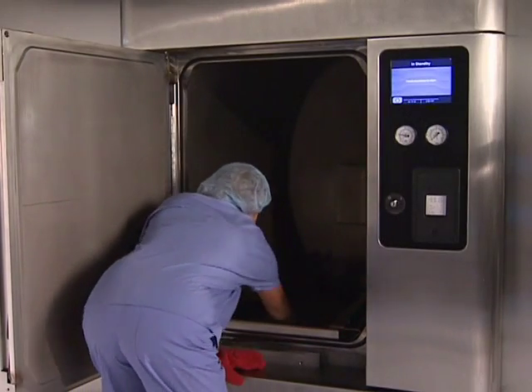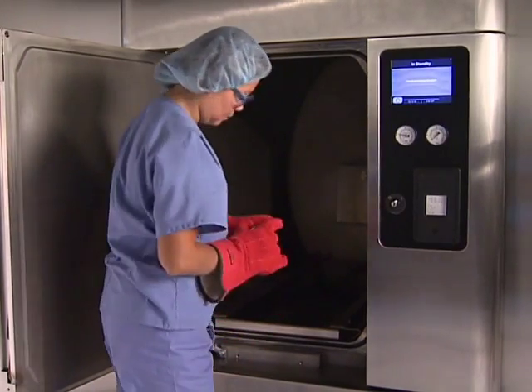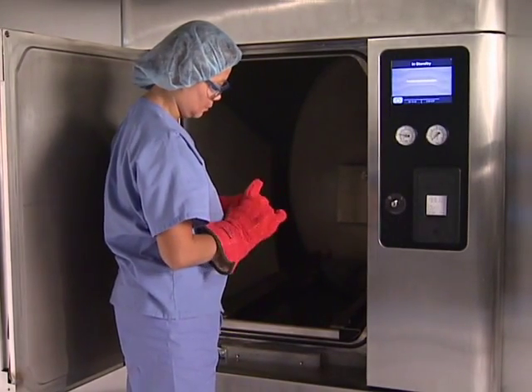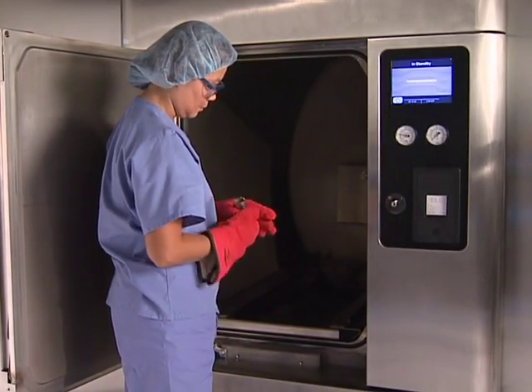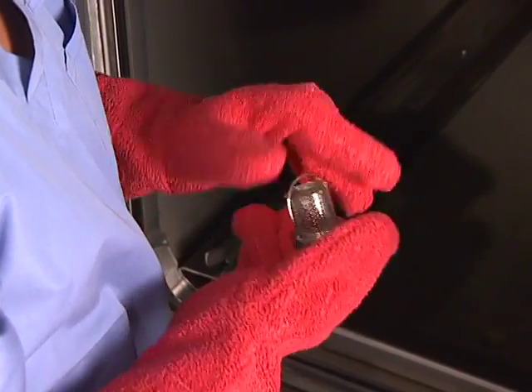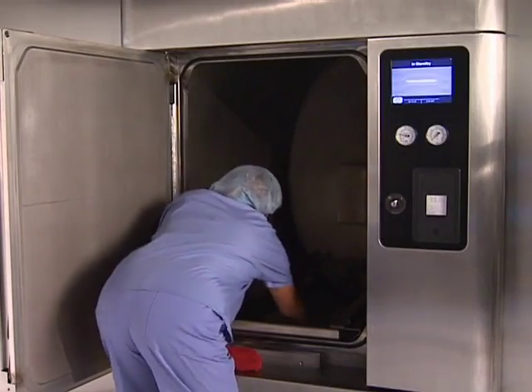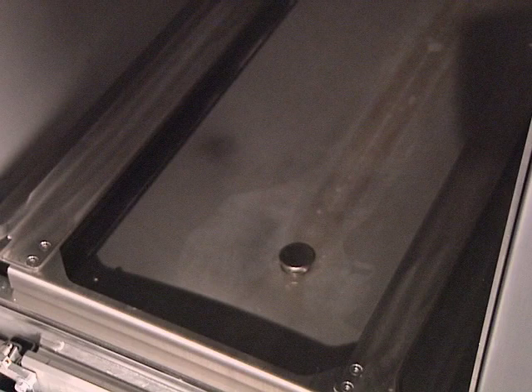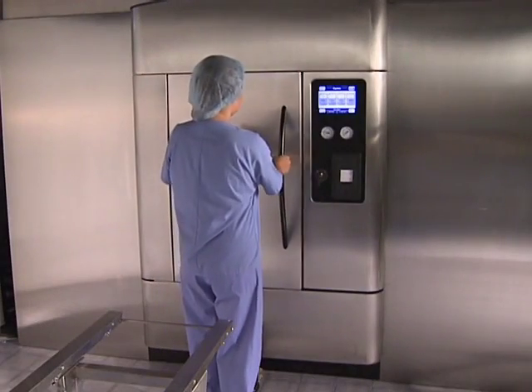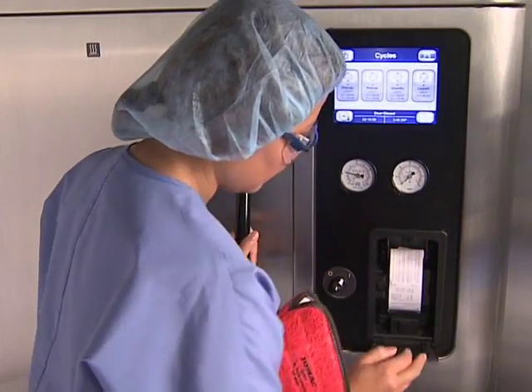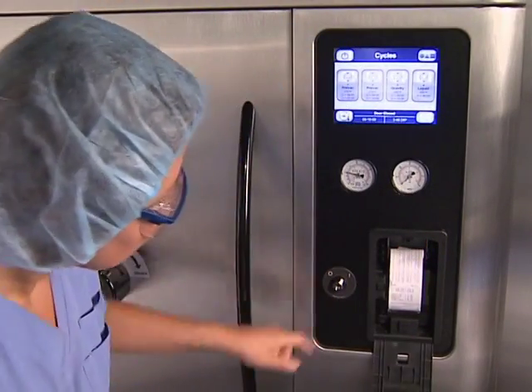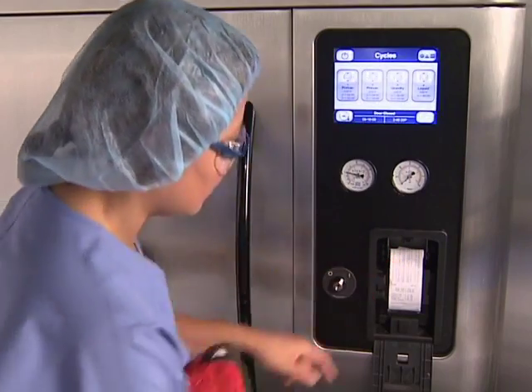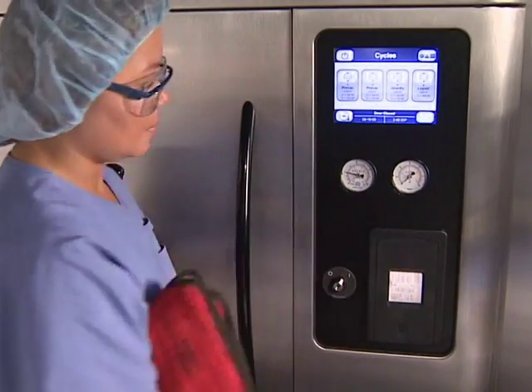Before processing a new load, you'll need to perform a few preliminary tests. First, check that the drain strainer inside the chamber is clean and in place. Caution should be taken as the door and chamber walls may be hot. Also, make sure that the chamber interior is clean and free of debris. Then close the chamber door. Next, check to see if there is enough paper in the printer for cycle documentation. Paper replacement will be covered in a later section of the video.